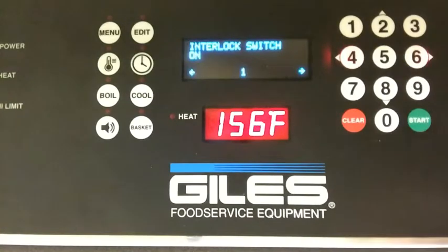We're going to press the number 6. That's the interlock switch. That's the ILS. That's the one that gives you the power failure message. If you were to turn that off, when you turn the unit on, if it's below temperature, it would immediately start heating, as opposed to giving you the message to press the start to begin preheating.